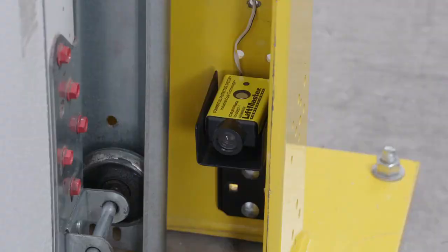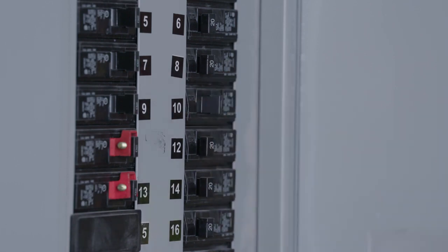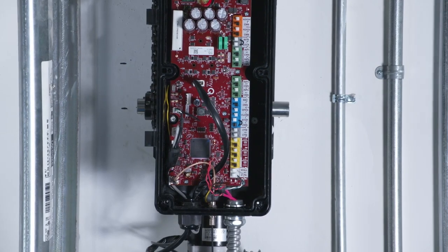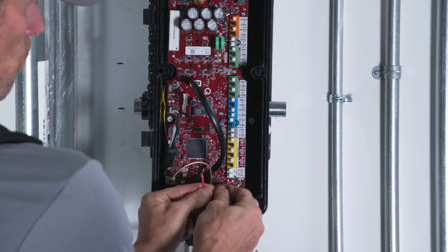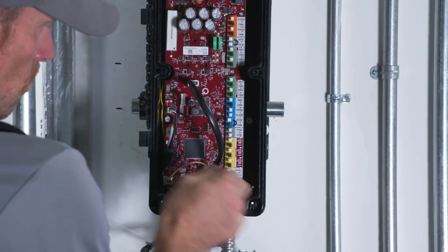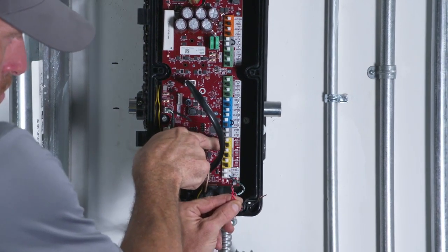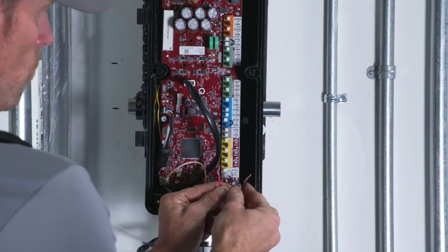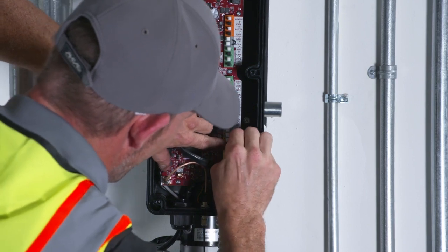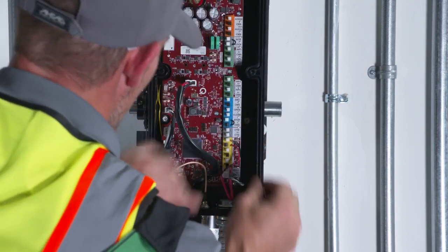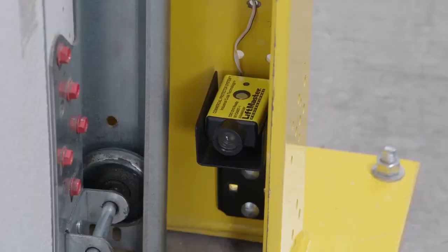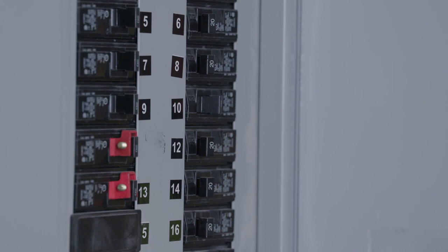Follow the steps to connect the CPSU devices to the operator. Make sure power is off to the operator. Route the wires from the CPSU devices into the operator. Locate the connectors for monitored devices. Twist together the wires for the edge-eye connection. Twist together the wires for common. Plug the edge-eye wires into edge-eye. Plug the common wires into common. Power must be on to check the alignment of the CPSU sensors. It's time to power on the operator. Connect power at the circuit breaker.